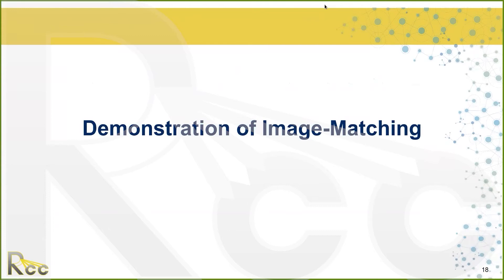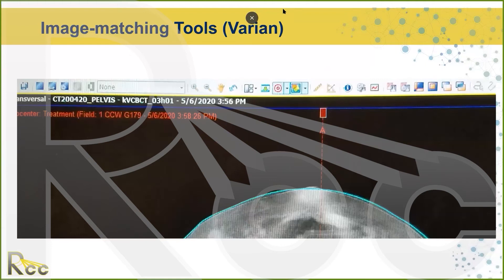Question: Is it possible to do CBCT if the equipment has no KV attachment? No, but there are places that have developed something called CT-on-rails, which gives you a CT scan without a KV attachment — though it's not as useful as cone beam because you lose the KV capability. However, for certain Varian machines, you can get a retrofitted KV attachment added onto your machine.